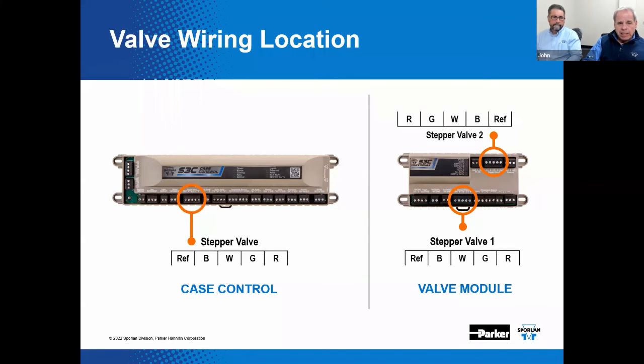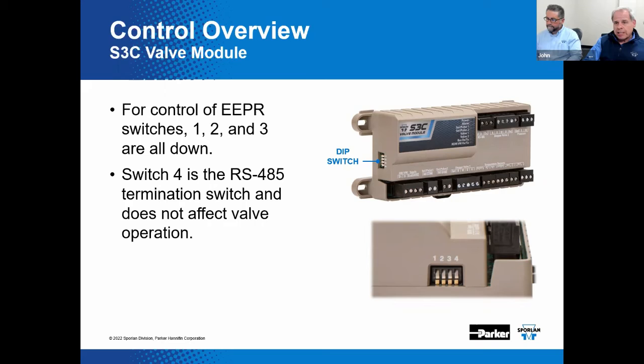Mm-hmm. Now let's take a look at this slide, which adds more detail to that whole situation. And what's going on here, John? So there are some added functions on the valve module. There are dip switches on the side of the module. You see them right there. There might be multiple valve modules on the job supporting different configurations. So that dip switch can provide an address or basically an identity for that module. It tells the valve module what type of valve will be landed on it or terminated to it. And if you note the position of the switches, with switches 1, 2, and 3 in the down position, an EEPR would be terminated on the valve module in the position of stepper valve 2.